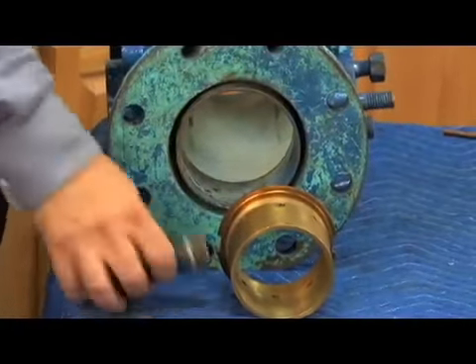If you could not get water coming out of those holes, yes, you may have to drop the body in again and clean it here, but that was extremely rare. But most of them you could clean out just by picking it through the hole, because that's where it tended to calcify, at the spot where that hole was.